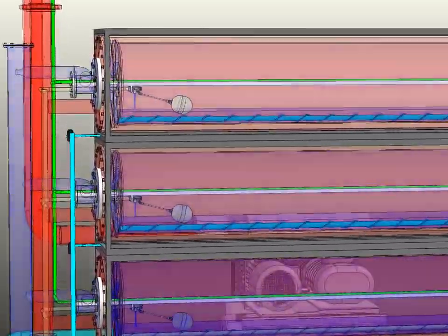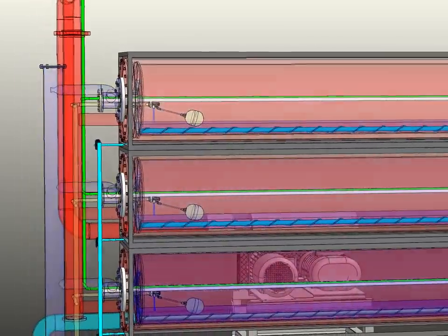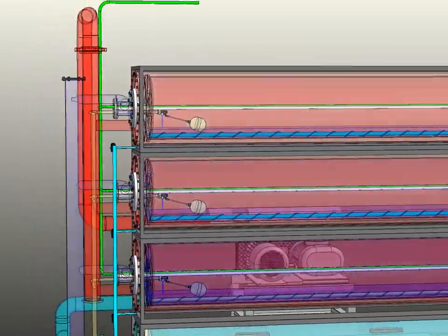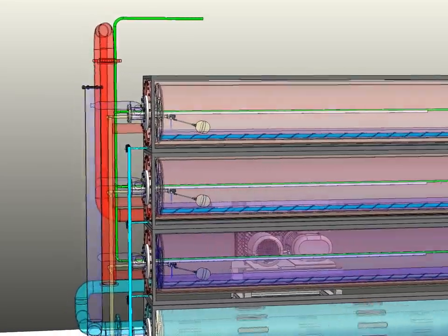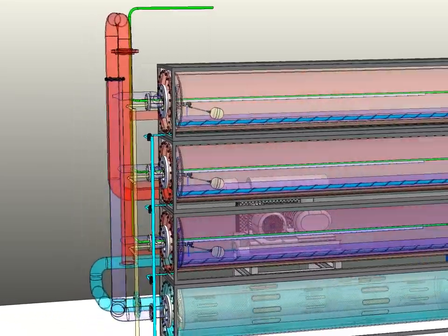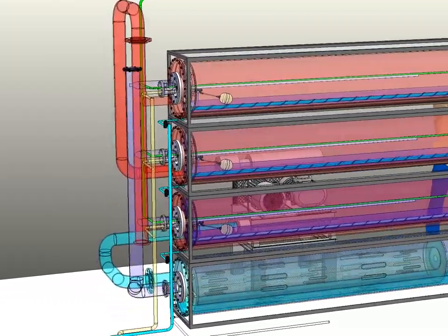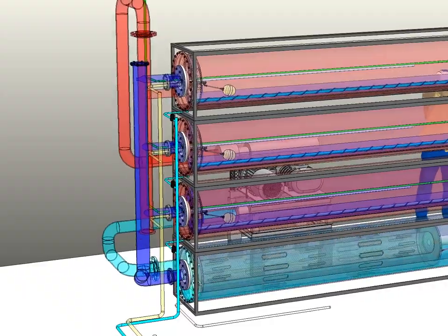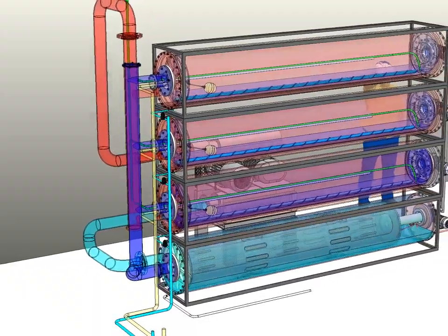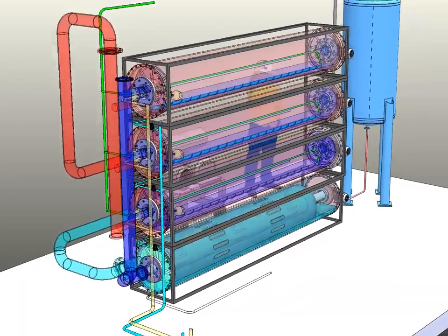Each DFE module includes a horizontal cylindrical body and an internally rotating evaporator drum. The drum at the bottom is filled with the evaporating solution. When the drum rotates, a film of solution forms on the inner surface due to wetting. When the drum body is heated from the outside due to the condensation of the heating steam on the outer surface of the drum, water evaporates from the film and secondary steam is formed.